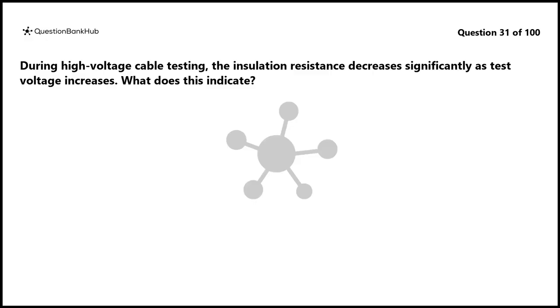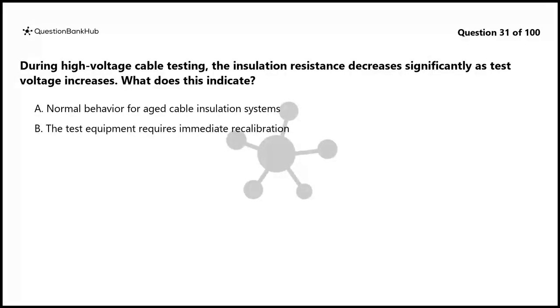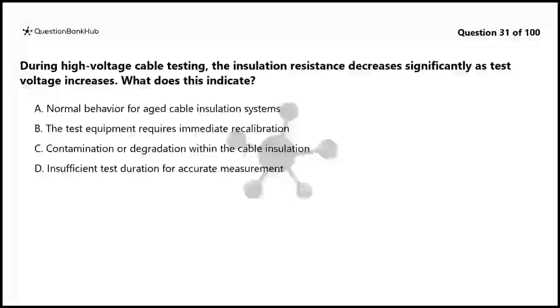Question 31. During high-voltage cable testing, the insulation resistance decreases significantly as test voltage increases. What does this indicate? A. Normal behavior for aged cable insulation systems. B. The test equipment requires immediate recalibration. C. Contamination or degradation within the cable insulation. D. Insufficient test duration for accurate measurement.